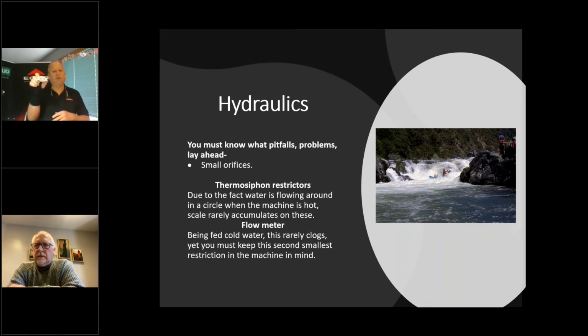In contrast to the flow meter, which on the inside, in order to hit the little windmill, the impeller, accurately, we run it through a small orifice, and it's like the second or third, depending on the machine, smallest orifice. However, it's cold fed most of the time. Yes, I'm sure there's plenty of people who will disagree with me because they're used to looking at one machine. But the fact of the matter is, usually it's cold fed, and this only becomes a problem like 5 years from now, 10 years from now, depending on how bad your water is. Anyway, next slide.